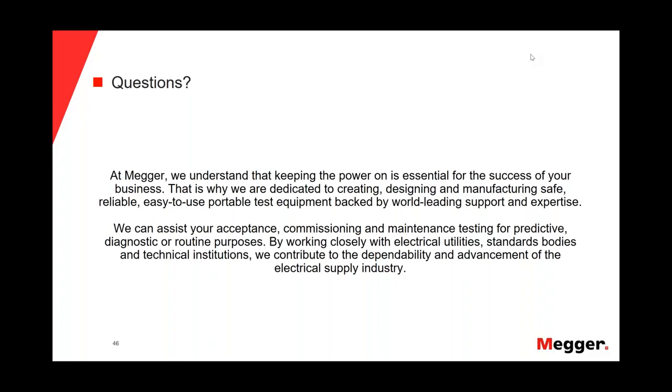Well, that depends a little bit how you do the PD testing. Normally, when we do single-ended measurements, it doesn't have that big of an effect compared to when you do make measurements in the return circuit. Then the condition of the neutral is very, very important, and corrosion would be detrimental. But also when we do single-ended measurements, if you have a really badly corroded neutral, it will create issues on your PD measurement.